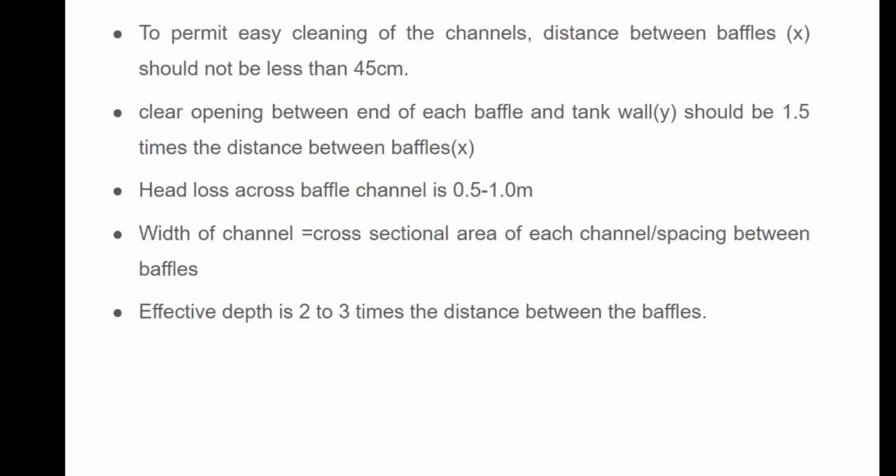To permit easy cleaning of channels, the distance between the baffles should not be less than 45 centimeter. All these values are very important while designing a mixing basin. Clear openings between the end of the baffle and the tank wall should be 1.5 times the distance between the baffles. These baffles are provided in such a way that the flow of water will be disturbed.